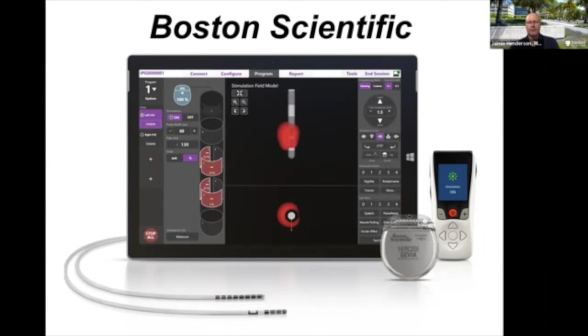You can see the lead and the electrical field is indicated in red. So it's really quite nice in that we can visualize what we're doing, we can steer it around, we can check for side effects and make it as effective as possible with the fewest side effects possible. And there have been some very good studies on this showing that indeed you can get better results by using this current steering and by using the differential current sources. And then on the right is what the patient programmer looks like. It's not too far different from the Medtronic one. It's maybe a little bigger. I think maybe a little ergonomically better than the prior generation of Medtronic.